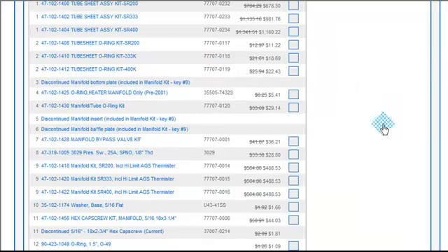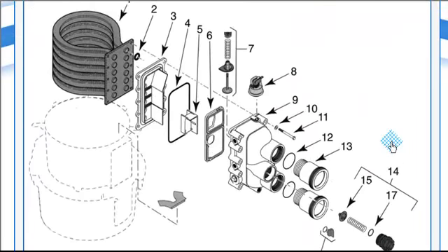All right, guys, so that's one way to help ensure that you don't dry fire your heaters. If you have a bypass system, turn off your pool pump, slowly turn off your ball valves, turn off the gas, loosen one of these nuts, and drain the drain plug, okay? And it does a couple of things. If the pressure switch works, it won't turn on, it'll go to PS. And besides that, you won't have water settling in this copper tubing, where the pH is going to fall out and corrode it. It'll help you on the life of the Sta-Rite heater.